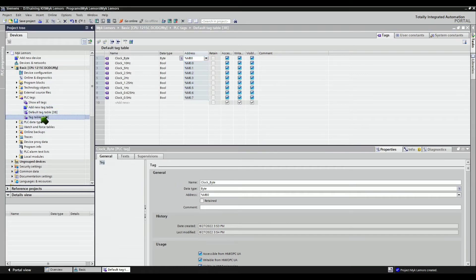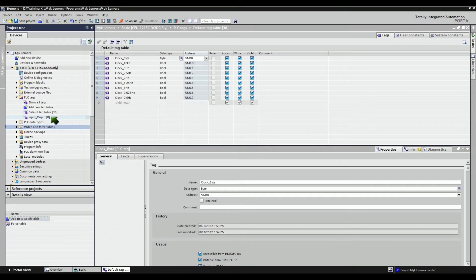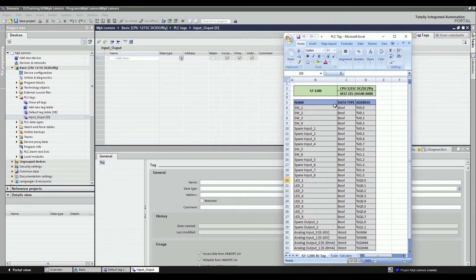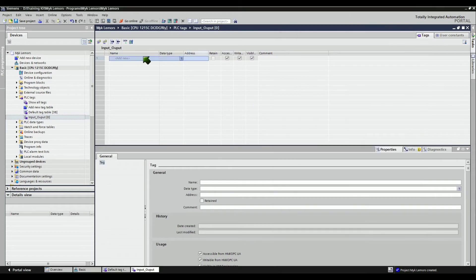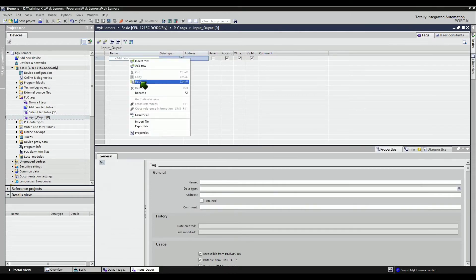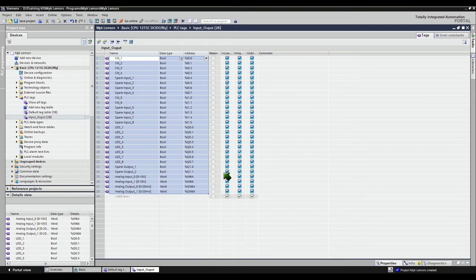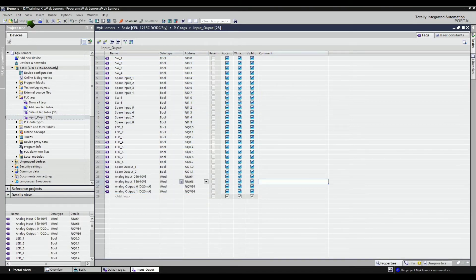You can also add a new tag table for your input and output addresses. When done, double-click to open. If the tag is ready, it's faster to just copy the tags from the Excel sheet and paste them to the input and output tags of the PLC. Input and output tags are now added on the PLC tag. Let's save the project.